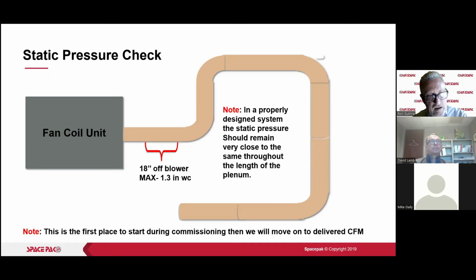Now keep this in mind, the 18 inches off the blower. That's going to be a straight area, and as we move through this, we'll cover all of the rules of the road. We're going to have 18 inches out of the blower before we have any fitting, whether that be a T or an elbow. The other thing I want to mention here is that on the new system, the J Plus series, the board itself is measuring the static pressure.